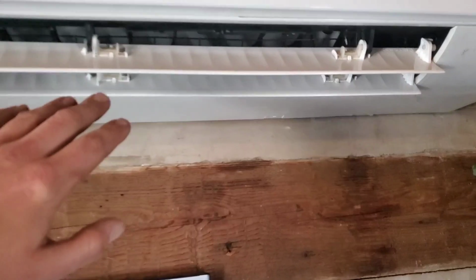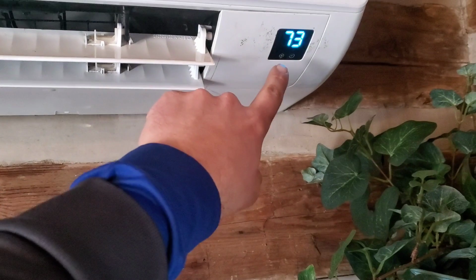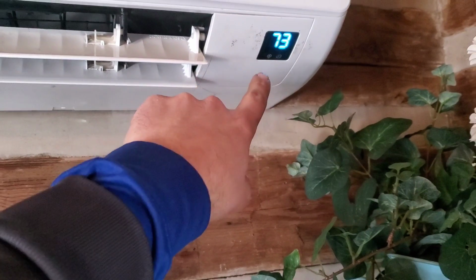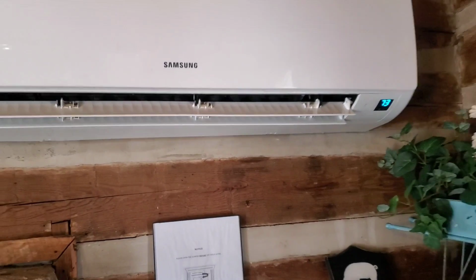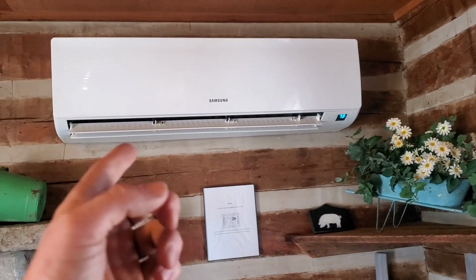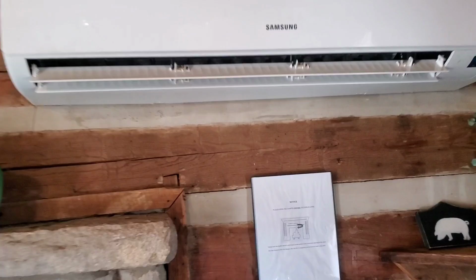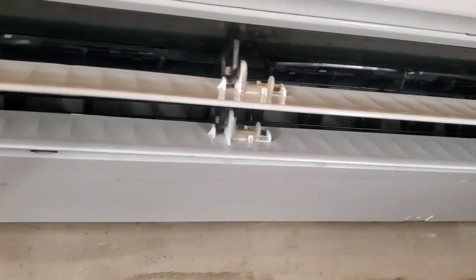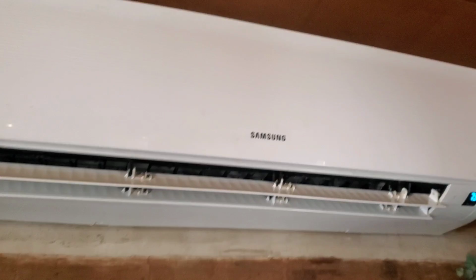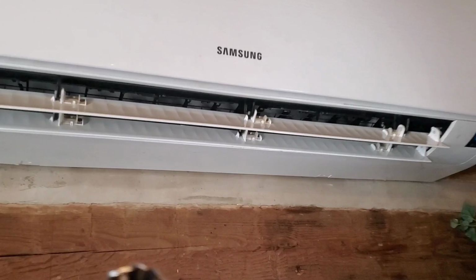So it's blowing some nice heat. It was set to 75. It's already 73 in here. So that's why it started to decrease its capacity, because it's already reaching temperature. Indoor fan sounds really nice now, so I'm loving that. Also, it's clean on the blower wheel. Show you guys the blower wheel. You don't see no dirt on that thing. Looking good.